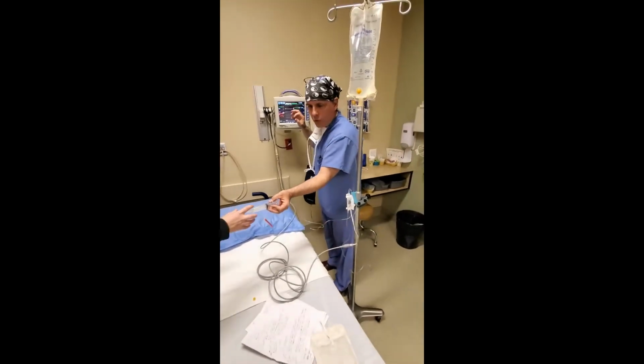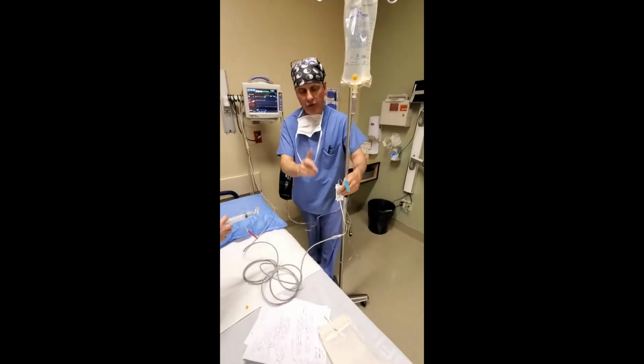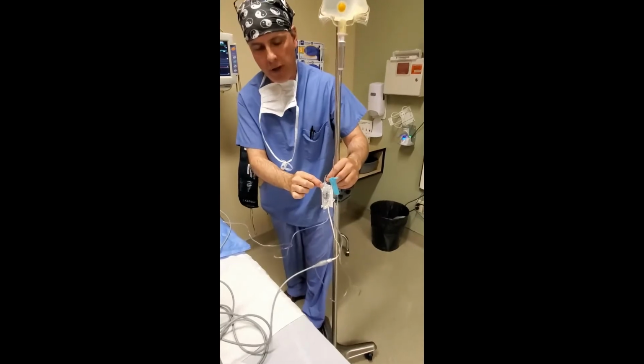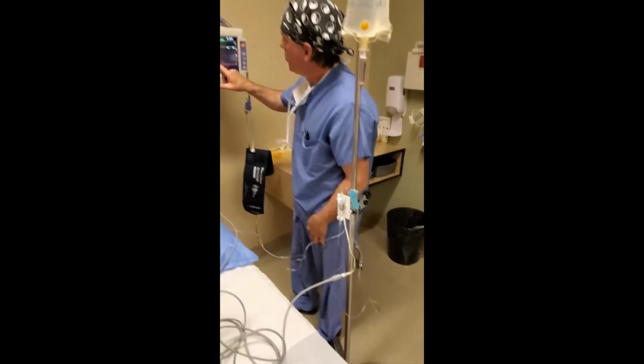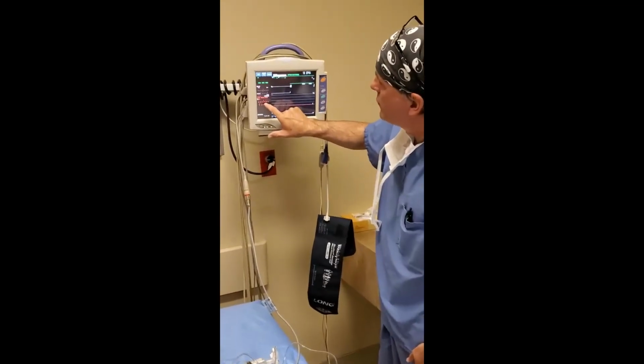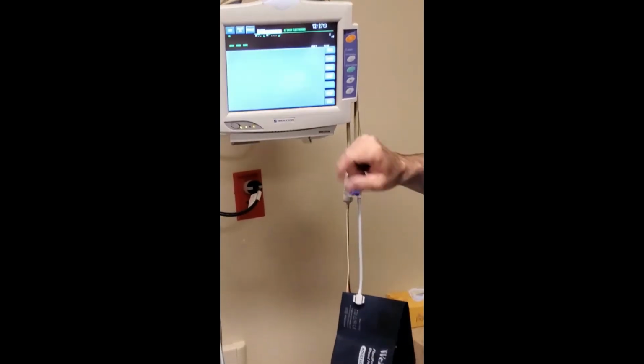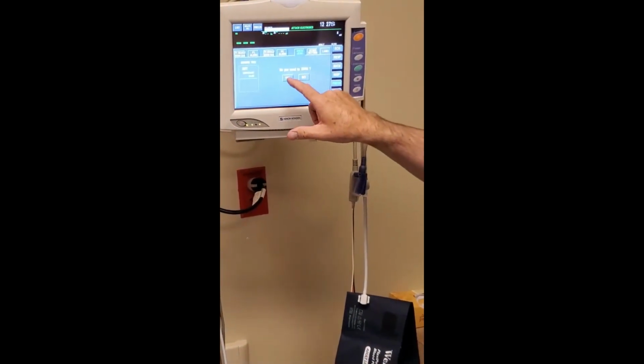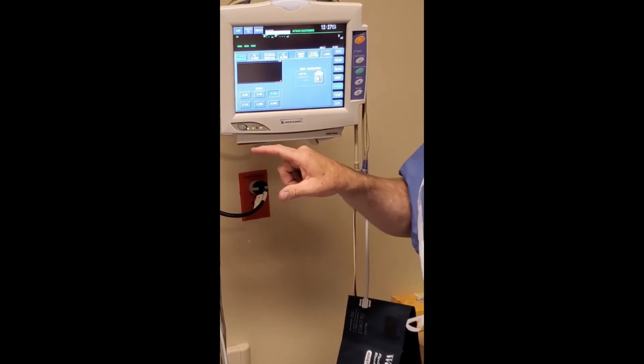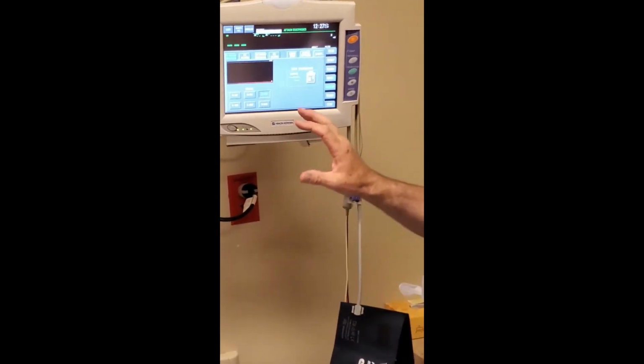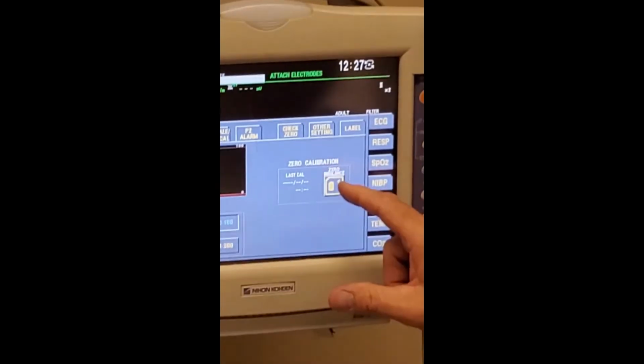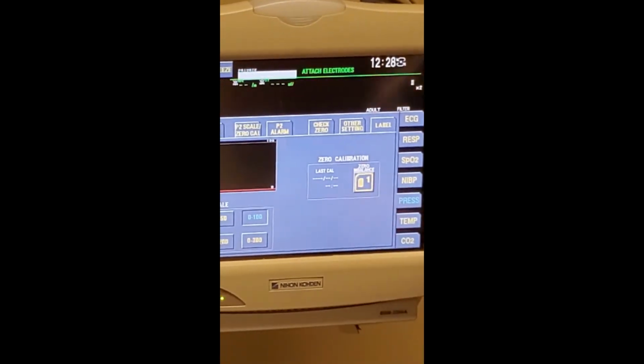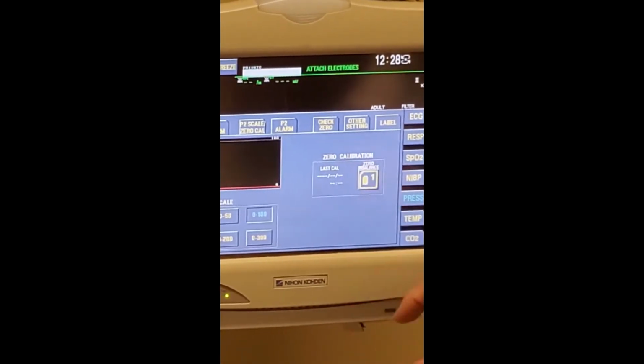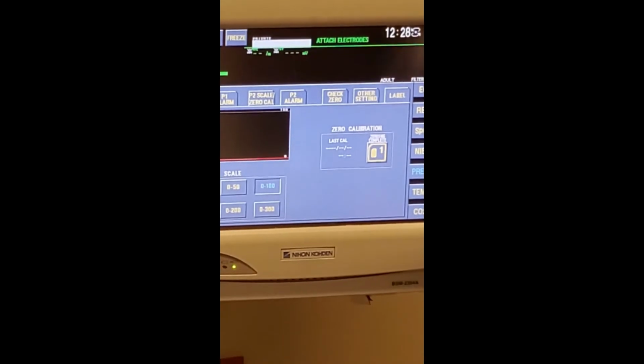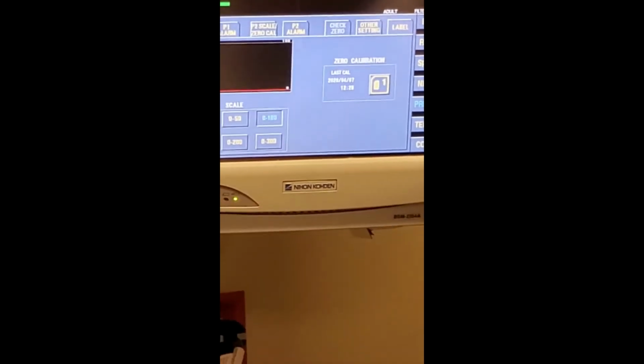So we're going to zero this real quick. The zeroing process is just a couple of steps: turn it off to the patient like we did here, then go to your monitor. It says zero imbalance—touch that, and it asks if you need to zero. Yes, we need to zero to make sure this is as accurate as possible. It says zero calibration, zero imbalance, so you touch this and it takes a few seconds. It says zeroing complete, meaning you're done. We can go back to the home screen, but then you have to return your transducer back to normal.